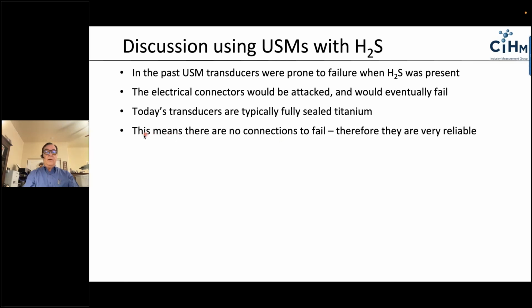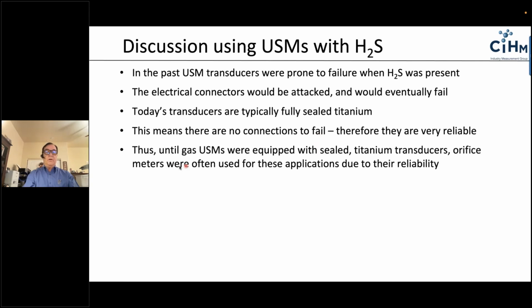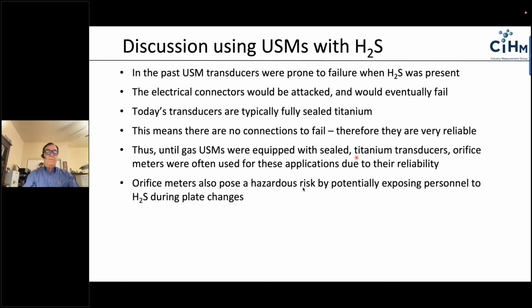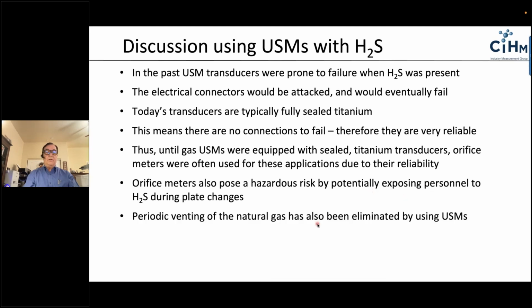So this means that they're much more reliable than we had, say, 10 or 20 years ago. Thus, with ultrasonic meters that are equipped with sealed titanium transducers, where orifice meters are often used, we can now utilize ultrasonic meters because they are much more reliable. Orifice meters also pose a hazard from potentially exposing personnel to H2S during plate changes, and we all know orifice meters have a limited rangeability, so plate changes are inevitable, whereas an ultrasonic meter has a much greater rangeability. Also of importance more and more these days is the venting of natural gas into the atmosphere, as well as the venting of H2S.